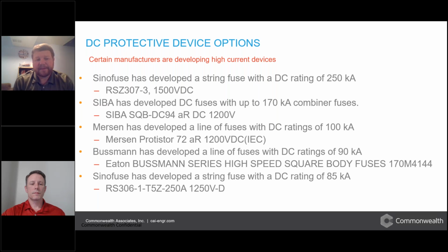So the one thing I want to mention is if you look generally for DC fuses, you're going to find DC fuses that are used in AC applications as well with time constants in that 10 to 15 millisecond range, and those aren't likely going to work for your application. These fuses here are built for battery energy storage systems by these manufacturers. They generally have L over R constants somewhere in the 500 microsecond to 1 millisecond range, which are more appropriate. And you'll also see some of the DC ratings be much higher.